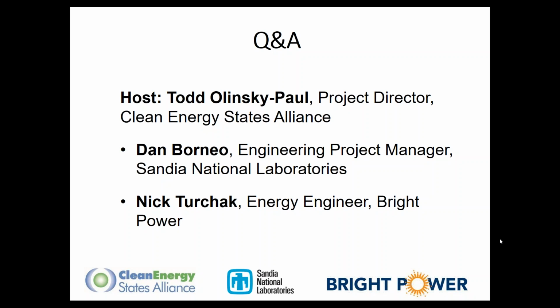So let's go back. For a 20 megawatt storage plant, could you discuss the RFP element for storage capacity in megawatt hours? So let's start with that. The megawatt hours would be for your application. So if it's, let's say, a frequency regulation application, that might be 15 minutes, so it would be a 5 megawatt hour system. However, if you want to do, let's say, energy shifting, well that might be a 4-hour system, so that might be 20 megawatts, which would be an 80 megawatt hour system. So what you'll have to do in your design process and analysis process is figure out what applications you're trying to serve, and that will dictate both the size in megawatts and the duration in megawatt hours.